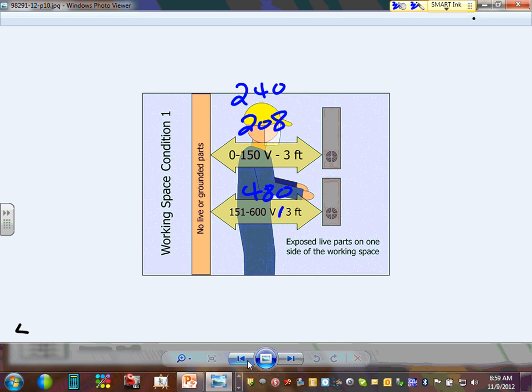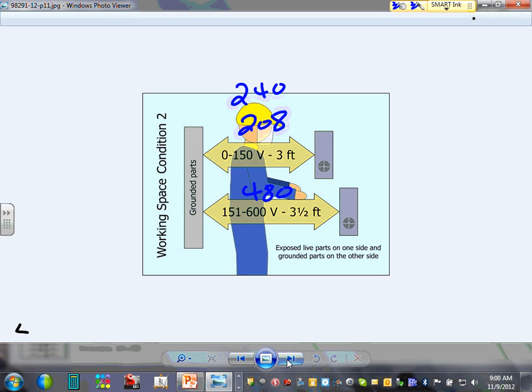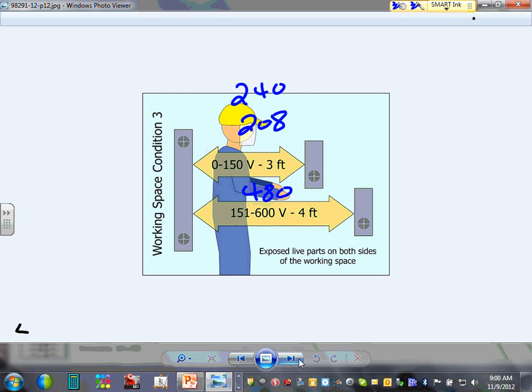I want to remind you guys, here's what the one before it was. If you don't have a grounded part, 3, 3, both of them, right? Now, if you go back here, you have 4, you added half. Now, the last one, if you have 2 panels facing each other, can you guys see that? 2 panels facing each other. Make sense? Same thing. 240, 208, 3 feet, continues to be 3. 480 jumps to what? 4 feet. Can I have a thumbs up, Chad? We fully understand the clearances in front of the panels.